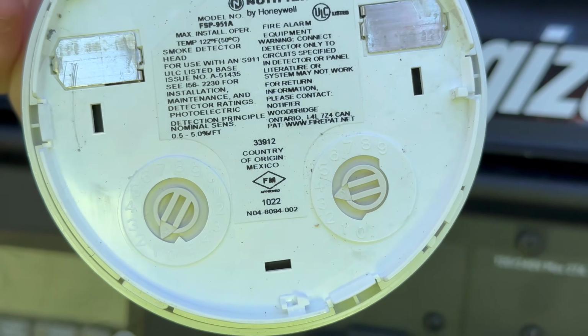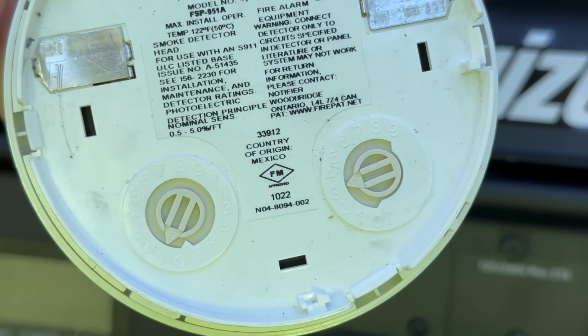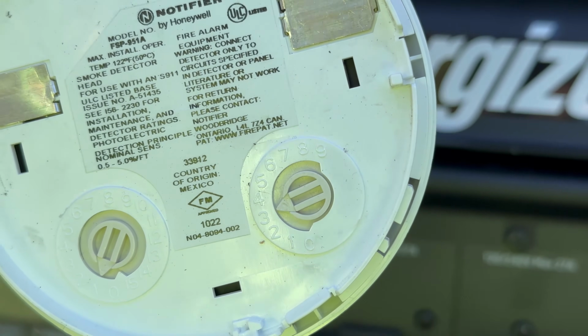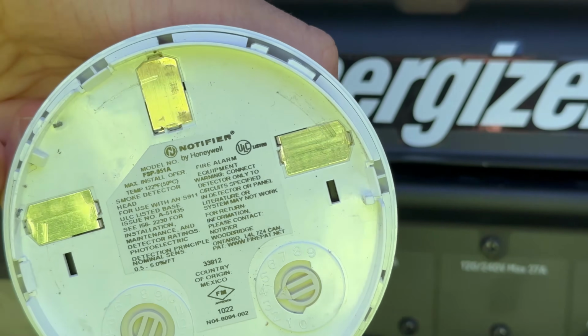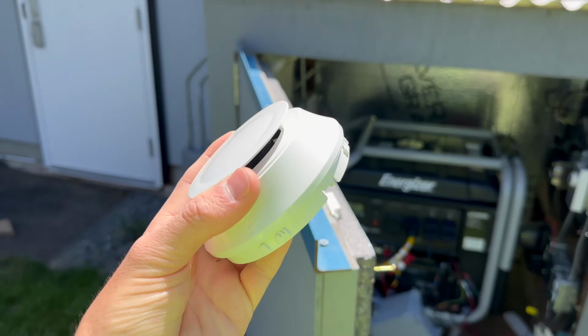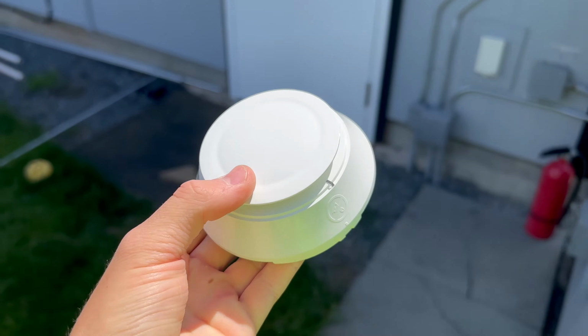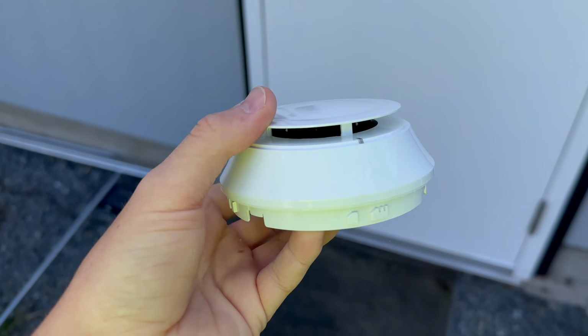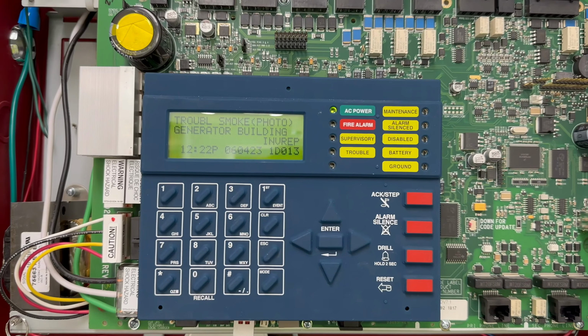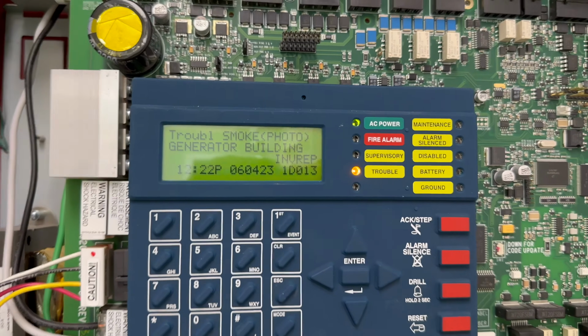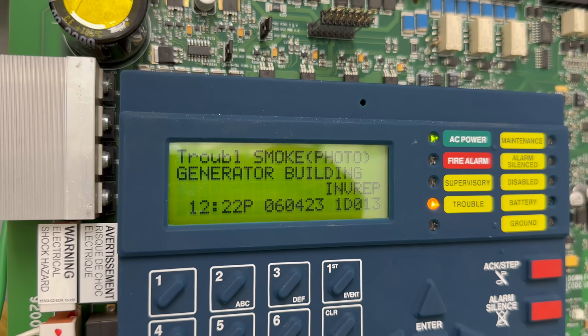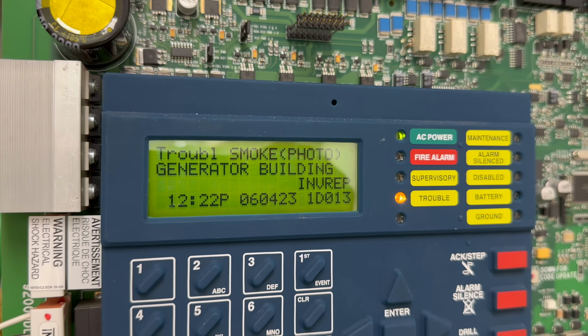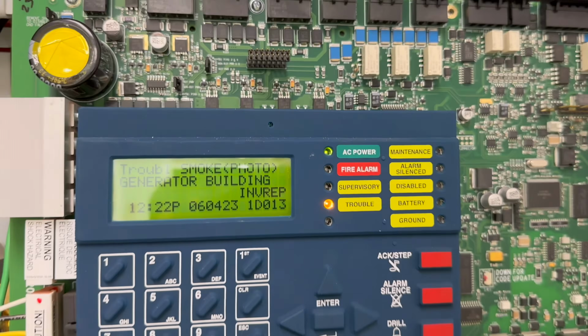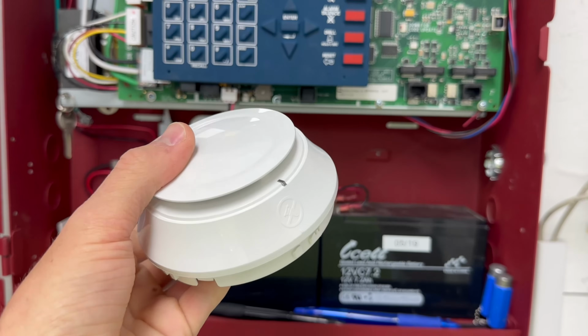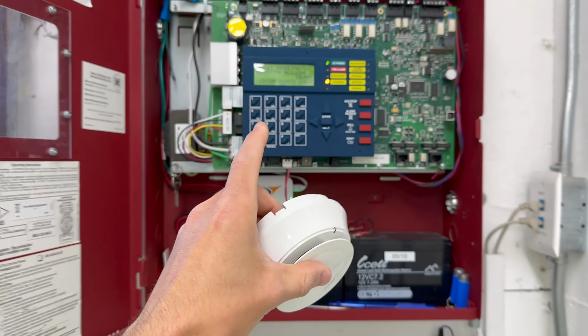There is a 1's place and a 10's place. As you can see, the 10's place is set to 1 and the 1's place is set to 3. That makes this device address number 13 on the system. It is a fully supervised system where, because this device is no longer seen by the panel, it will put the fire alarm system into trouble, which we can acknowledge. And you can see we have smoke, photoelectric smoke detector, generator building, invalid reply, which means the system has tried to communicate to this device, though it has failed to reply to the fire alarm system.